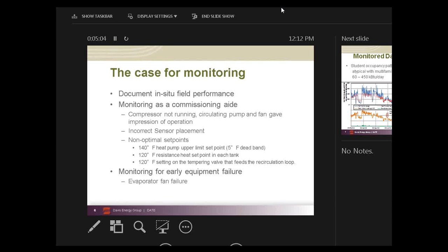The field installer did not notice the error because the evaporator fan and circulator pump were both operating continually, giving the sense that the unit was operational. And the only way that they would have noticed is if they had remained nearby for a long period of time to notice that the unit wasn't shutting off. The installers were not familiar with the technology, and the control interface didn't give any kind of immediate feedback or warning light to alert to the issue.